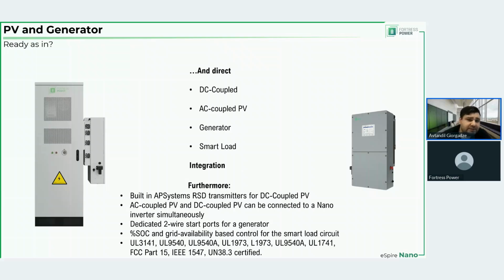The system supports direct DC coupled PV connection, AC coupled PV connection, generator connection, and a smart load connection. So you can connect a DC coupled PV to the system. You can connect AC coupled PV, either AC coupled PV alone or in conjunction with the DC coupled PV. You can connect the generator to the system, and it will provide the pass-through to the loads when the generator is turned on, and it will also charge the batteries when the generator is turned on if you allow it to. It has a generator auto start function, so 2-wire start is an option with this system.